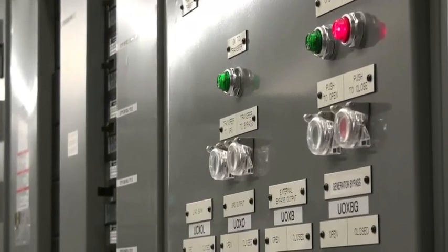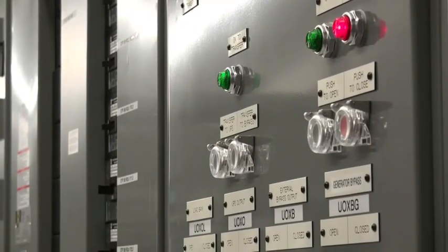The first patent is an isolated redundant bypass system. It's a bus, and it's for both our generators and UPS, and what it allows us to do is to move live load from one UPS to another UPS. So when we go on maintenance, instead of having to go on generators, we stay on utility power and we transfer the load to an entire separate UPS system, and then we do maintenance, and nobody else offers that, and it's a great thing for our customers because they know that their entire load is protected by UPS power.